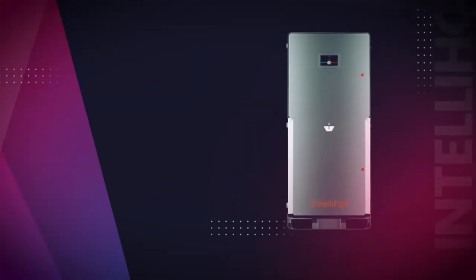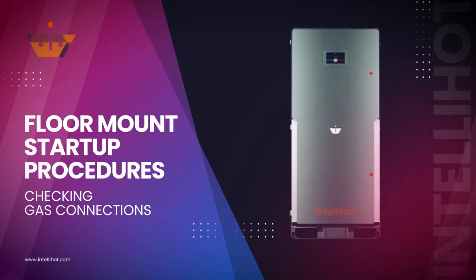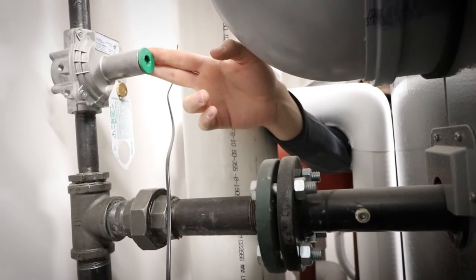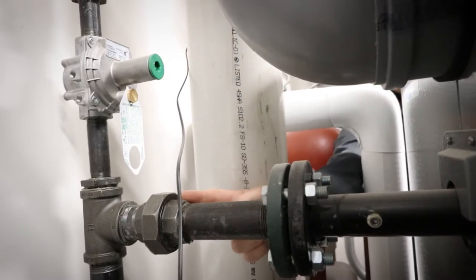In this video, we are going to check the gas side of the floor mount installation. We recommend a dedicated gas pressure regulator be installed for each unit. This regulator will ensure that the unit sees a constant gas pressure regardless of which other gas applications are running.